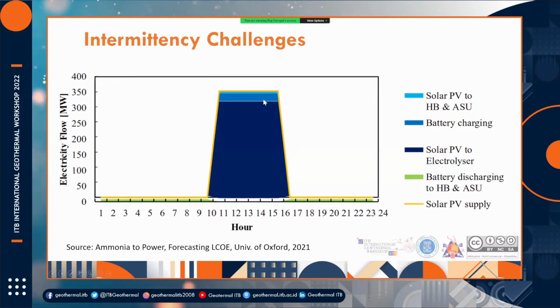Even with the battery in place, in the evening when solar is not available, we need to run the ammonia plant at very low capacity, turned down to like 30% or even 10% of nameplate capacity. This is a challenge because running the ammonia plant at very low capacity consumes much higher specific energy. And an ammonia plant cannot be shut down, because it would take 2 or 3 weeks to restart. So we need to keep the ammonia plant running at all times.